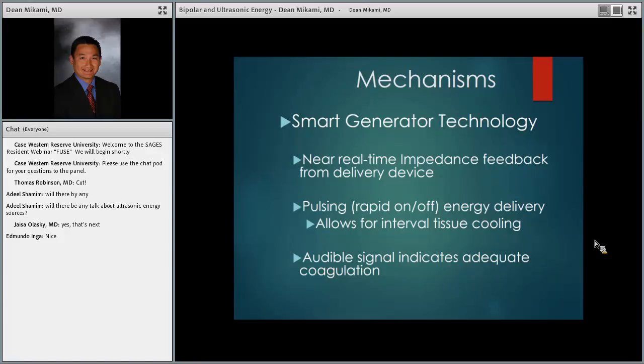A lot of times I get asked this question: why is it when I place my bipolar instrument on a vessel and I seal it, I hear the beep and I get a change in resistance? I say, that's correct. But why is it when I put it on again, it doesn't go instantaneously to the beep? It takes a few seconds again, right? You think about it, and you say, it should really seal again because the vessel's sealed. And the answer is it's seeking a change in resistance. So if you start there and the ohms is, say, 50, and by the time you fire your first cycle, it goes up to 400. And then you put it on again, but now the resistance is 400 at tissue level. It's trying to reach 800, right? So it's going to really try to seal down more. So if you're really worried about large vessels and you want to do a double seal, you shouldn't put it on the same area. You should move off that vessel just a little bit to the left or right, and then seal it at multiple spots if you want multiple seals.